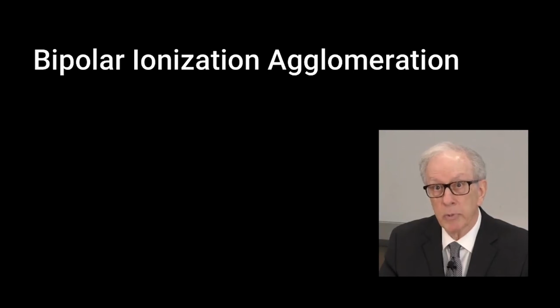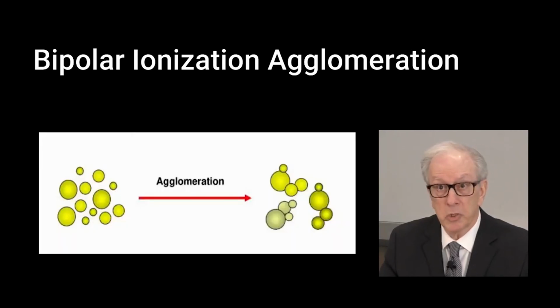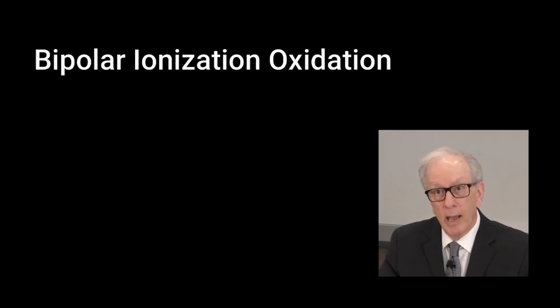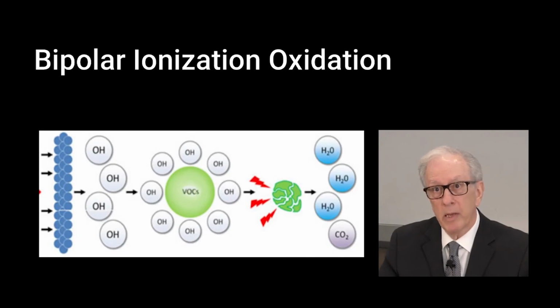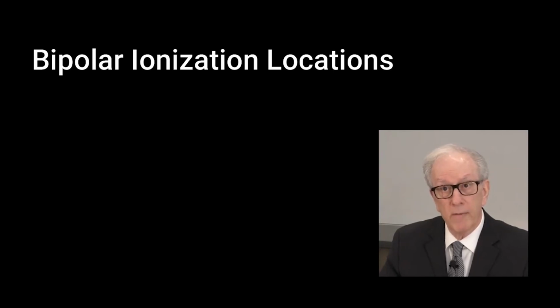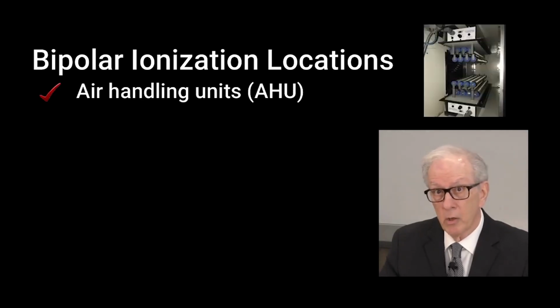The second method is called agglomeration. This is where oppositely charged small ions, such as dust and the pollutants I mentioned before, combine to form larger, heavier particles that can actually be filtered out by the air handling units or simply drop to the floor out of the breathing zone. Third is oxidation. Bipolar ions surround VOCs, breaking down their hydrocarbon chains and reducing these complex compounds to immeasurable amounts of CO2 and water.